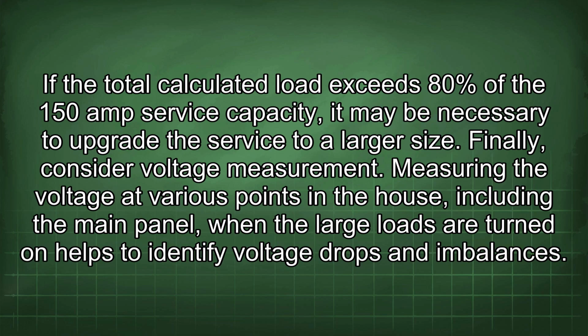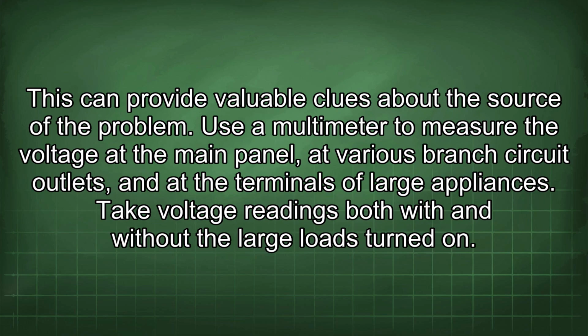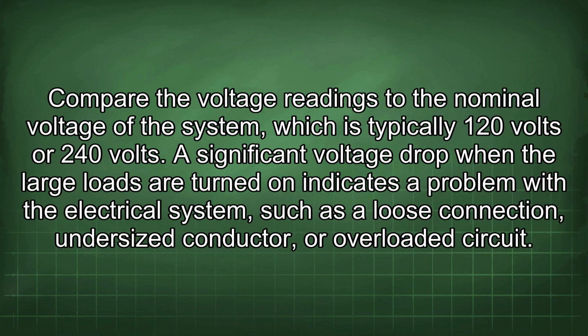Finally, consider voltage measurement. Measuring the voltage at various points in the house, including the main panel, when the large loads are turned on helps to identify voltage drops and imbalances. This can provide valuable clues about the source of the problem. Use a multimeter to measure the voltage at the main panel, at various branch circuit outlets, and at the terminals of large appliances. Take voltage readings both with and without the large loads turned on. Compare the voltage readings to the nominal voltage of the system, which is typically 120 volts or 240 volts.